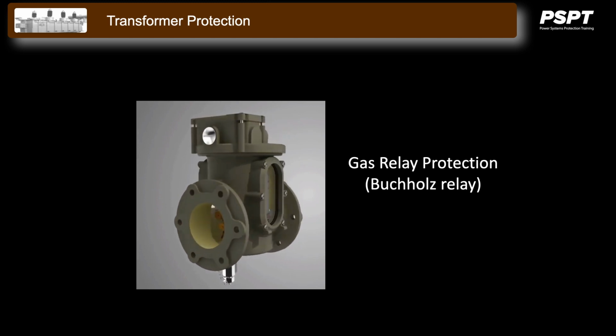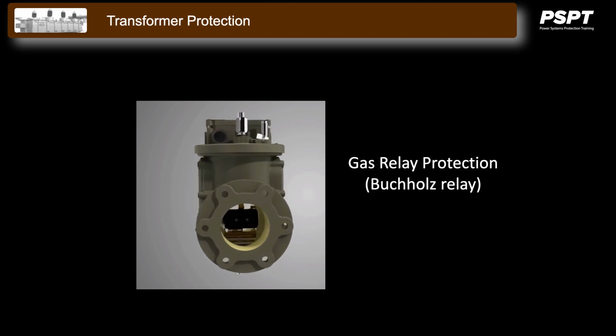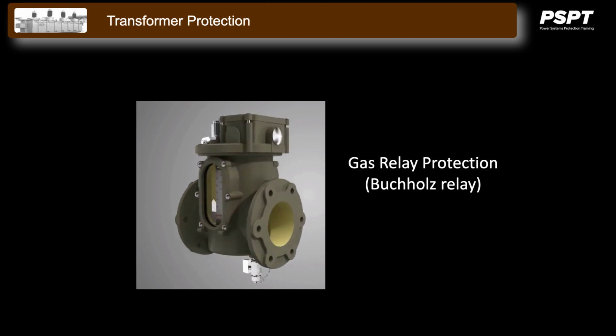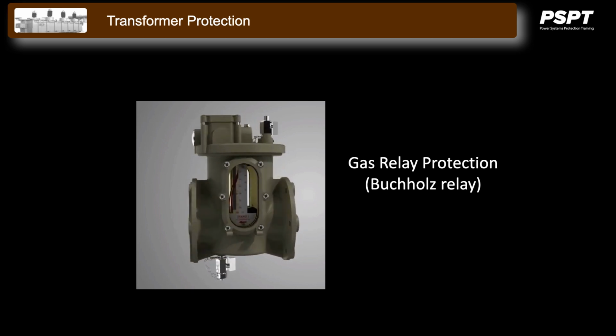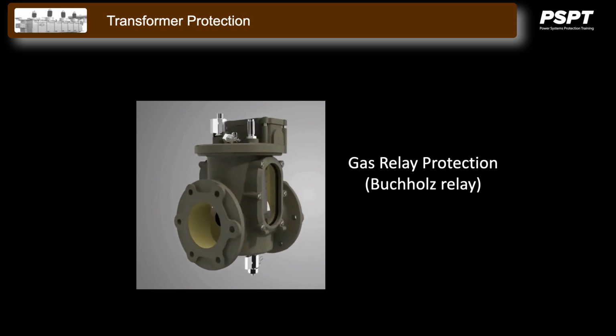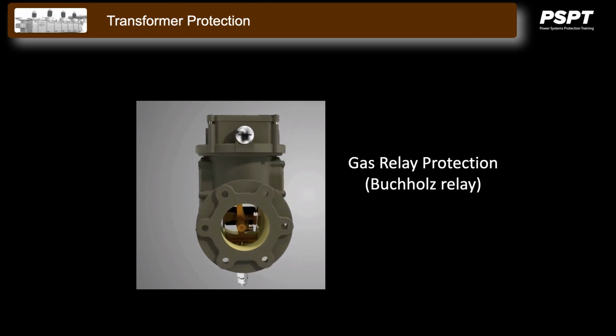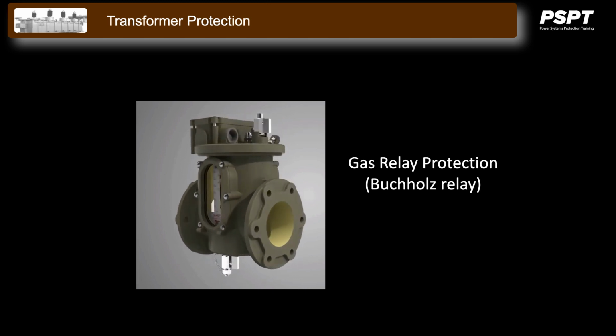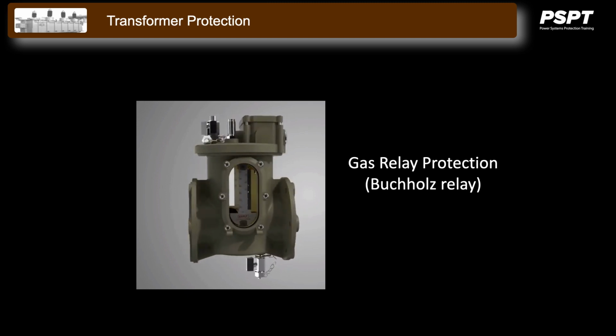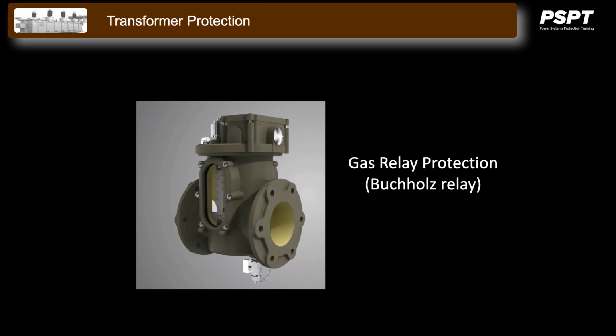The last protection device to be discussed in this chapter is more mechanical than electrical, with pressure and flow as the initiating variables measured mechanically. This relay measures the rate and volume of gas accumulation in an oil-immersed transformer. It was developed by Max Buchholz in 1921 and has since been known as the Buchholz relay, applied to large power transformers since about 1940. It has been slightly modified over the years, but the basic principle of operation has remained unaltered.